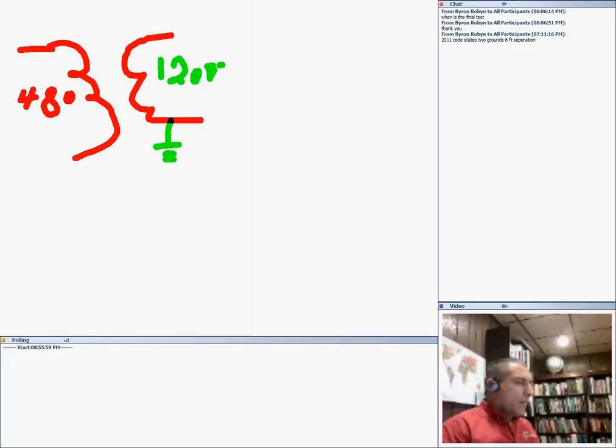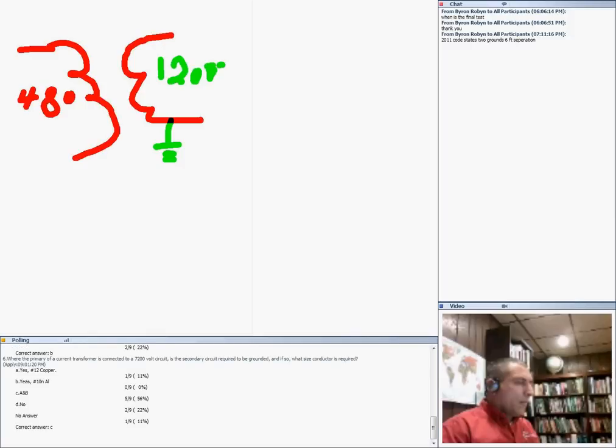Okay, my friends, I know you are up, guys, but bear with me a second here. Perfect. Okay, I'm going to share the results with you guys. The one to mention, guys, is the last one, which talks about the voltage on the primary. If the voltage is more than 300, then the secondary must be grounded. For control transformers, that's a big deal. For safety reasons, if your primary voltage is 300 or less, which covers 208, 240, 120, you don't need to ground the secondary. But if it's more than 300, then you have to ground it. So that's what I want to show.